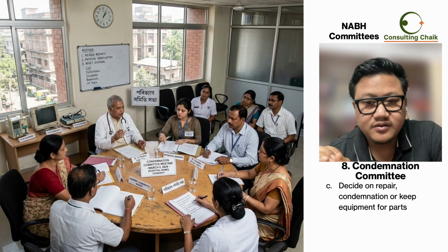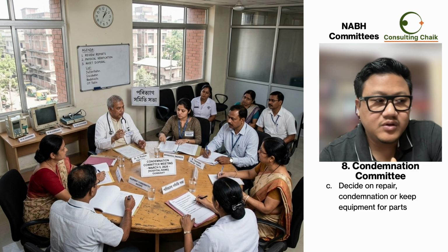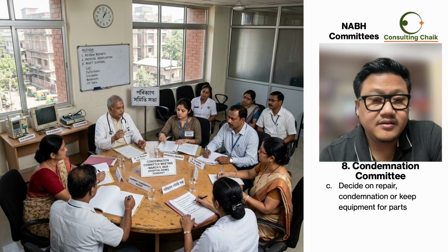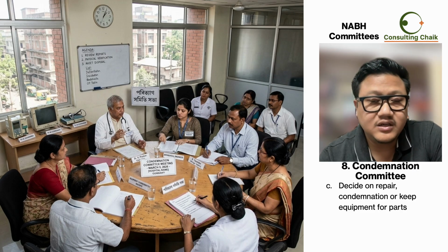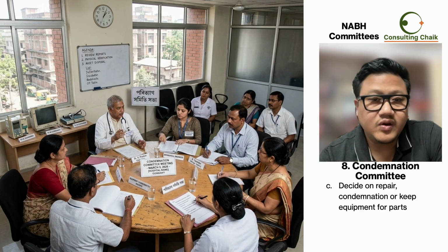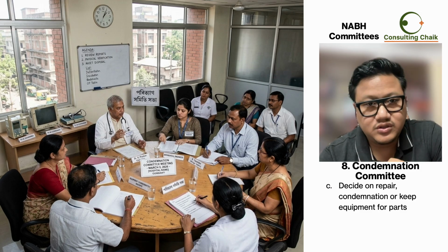They also need to decide. So whenever a department forwards that we have to condemn this equipment because it is not working, the team of biomedical engineers make a call whether to repair the equipment so that it can be used for another 6 months, 1 year or 2 years, or condemn the equipment because nothing can be done about it. Or third, the equipment cannot be repaired, but its spare parts can be used in other equipment.